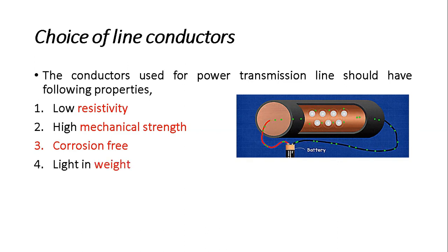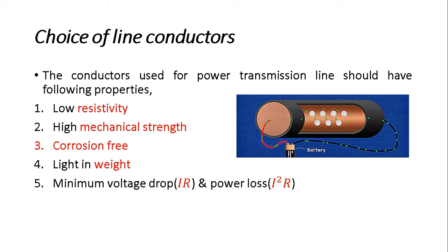The third property is that it should be corrosion free. The fourth is it should be light in weight — otherwise, if the conductor weight is more, we need heavier tower structures, which is not economical. The fifth criterion is minimum voltage drop and minimum power loss. Minimum voltage drop gives us high receiving-end voltage and improves voltage regulation, while minimum power loss improves transmission efficiency.